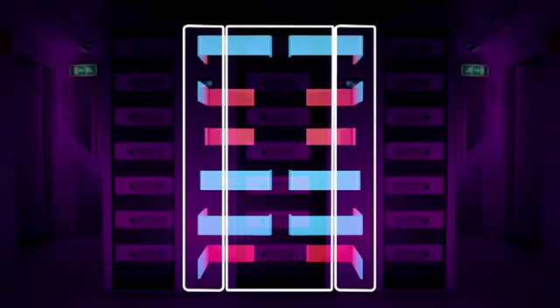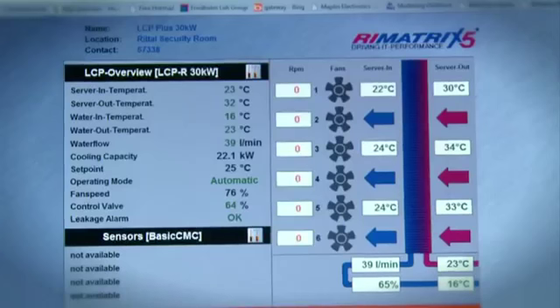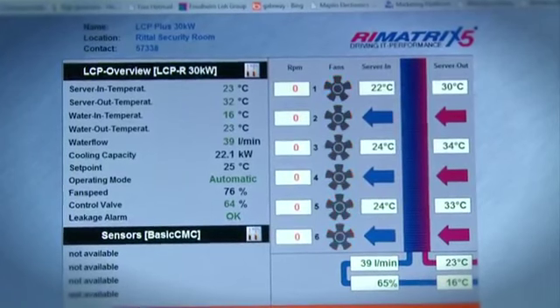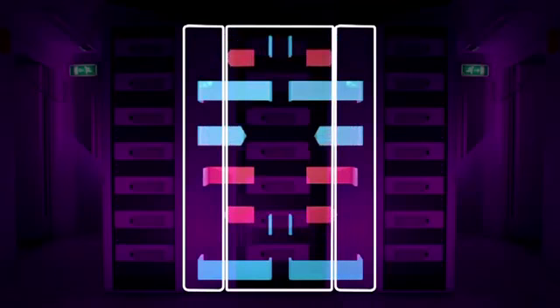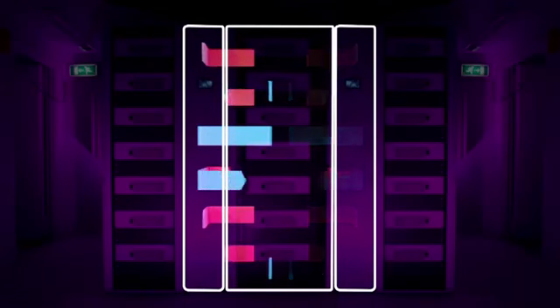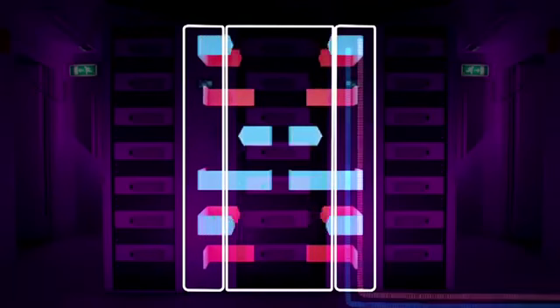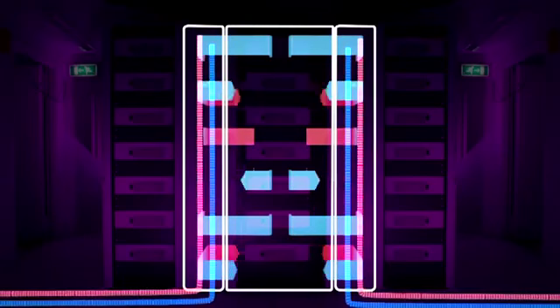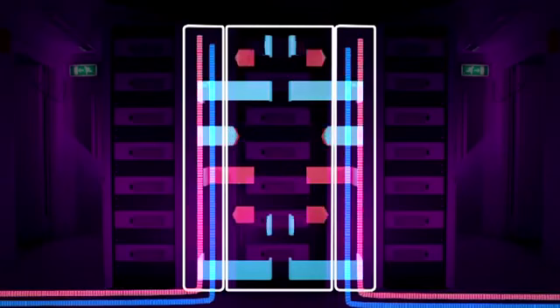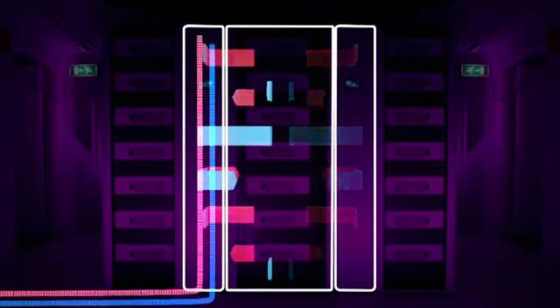N+1 configuration is very simple to implement. And in the unlikely event of an LCP failure, the secondary LCP is always available. To increase the robustness of the system even further, each LCP can be fed from a separate water supply, so even if the chiller fails, there's a backup supply.